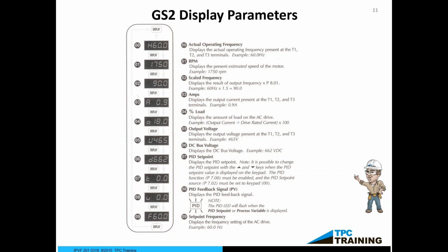And if you look at that DC bus voltage, earlier I said that the DC bus voltage is a great indicator of the health of the machine. So if you don't walk away with anything else today, just know that the DC bus voltage is 1.414 higher than your input voltage. Now, we could talk about PID, proportional, integral, and derivative. It's too short of a seminar or webinar to talk about PID set point. That's quite a lengthy conversation and takes an hour or two or better to talk about that.